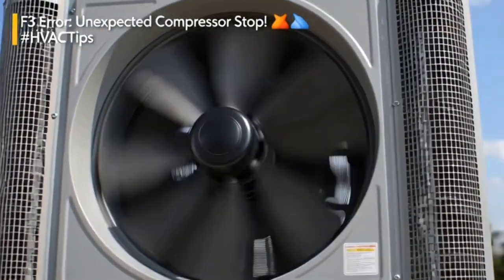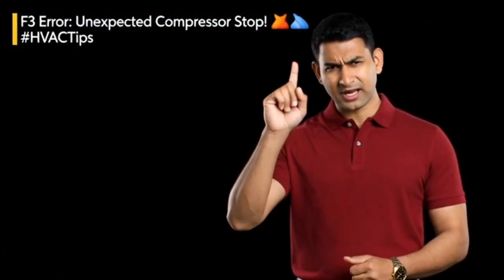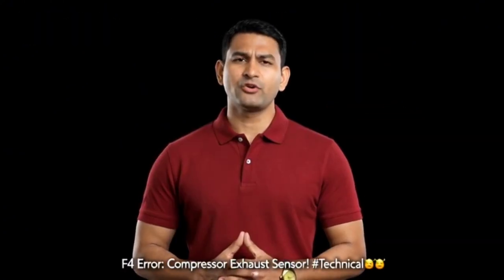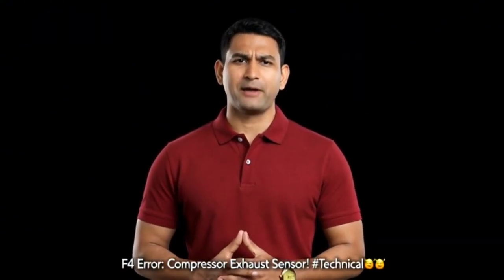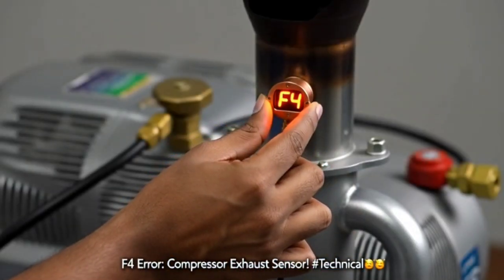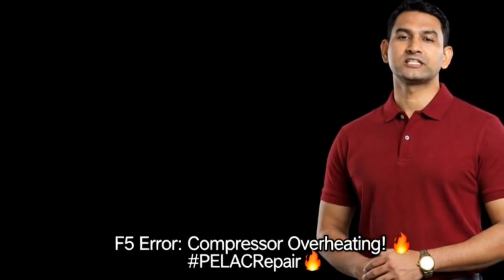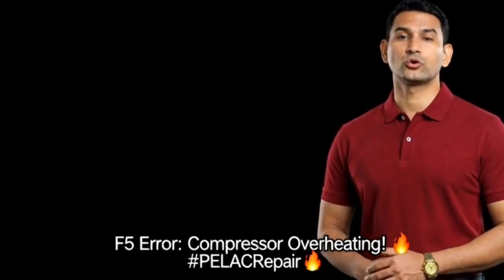F3 means the compressor suddenly stopped during operation. Check the wiring. F4 indicates a faulty sensor on the compressor's exhaust pipe. F5 means the compressor is too hot. It needs service or cooling.